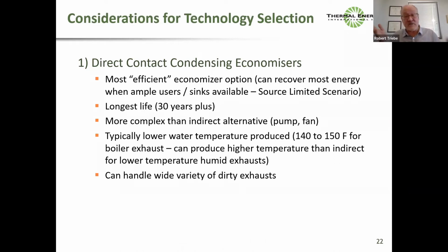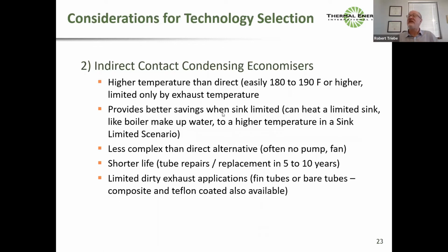And of course, a direct contact system is a wet scrubber, so it can handle a wide variety of dirty exhausts as well. So those are a couple of the considerations for a direct contact condensing economizer. For an indirect contact condensing economizer, now my water is in a fin tube and the condensation occurs on the outside of the tube. I can get a higher temperature much more easily. So if I've only got a small heat sink, I've got this much waste heat available, but I've only got this much user. Now my savings are not dependent on how much heat I can recover. It's dependent on how hot I can make the user.